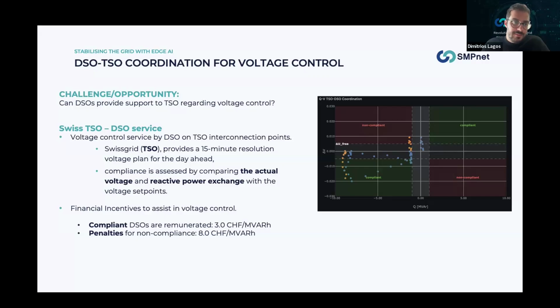So the Swiss grid, the TSO, every day sends a profile with 15-minute resolution of a voltage plan for every point where a high voltage to medium voltage transformer is located, which are also the connection point of the DSOs. So the DSOs have to follow that voltage profile, and according to the measured voltage value, they have to either inject reactive power to the transmission system or absorb.